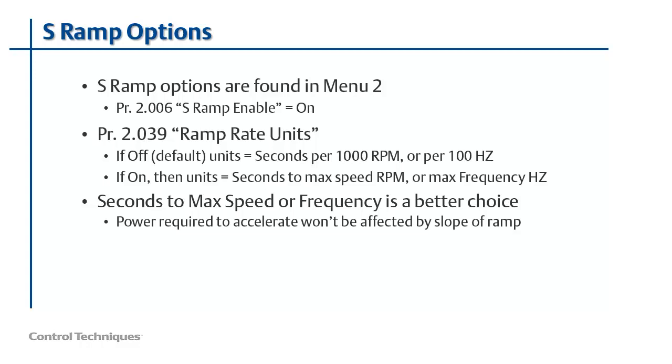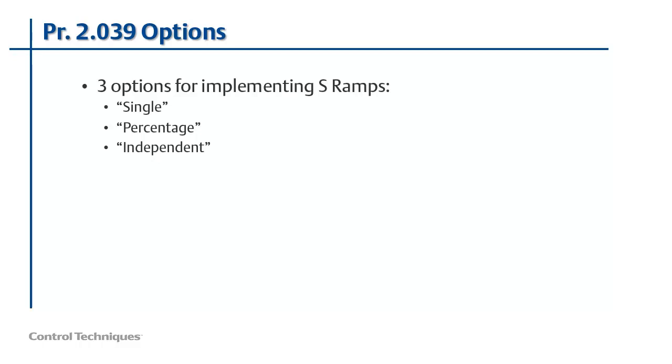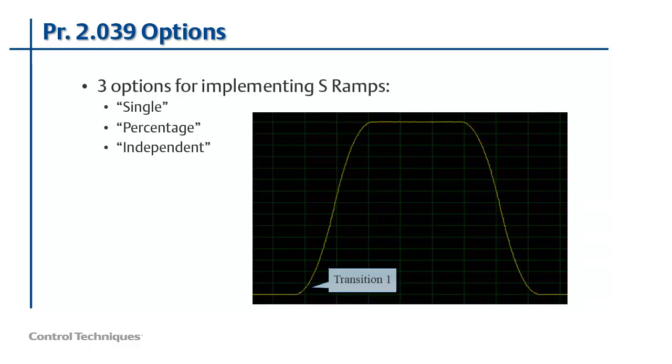Now let's watch as I demonstrate the three different options for S ramps. Parameter 2.039 is used to choose which of the options for S ramps you'd like to use. The three options for this parameter are single, percentage, and independent. To make this somewhat clearer, another term for S ramp acceleration is jerk. Jerk is a physical property common to electromechanical systems and it is defined as the rate of change of acceleration. Acceleration, you'll recall, is defined as the rate of change of velocity. Jerk is employed during the four transitions that we looked at earlier.